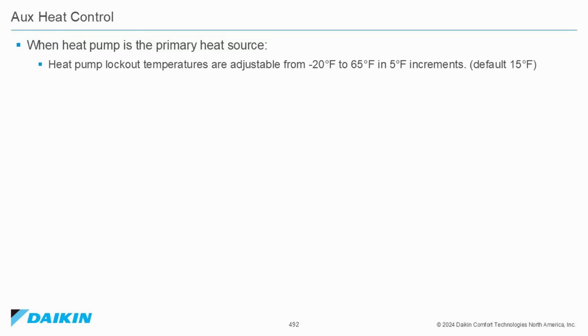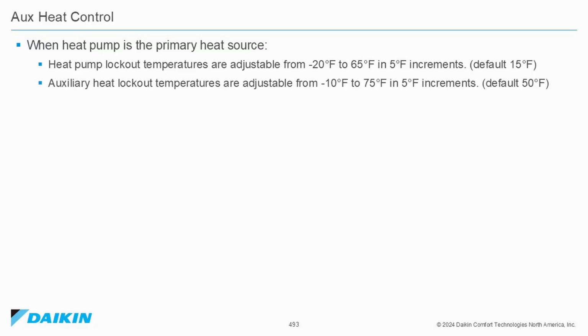Auxiliary heat control. When the heat pump is the primary heat source, the heat pump lockout temperatures are adjustable from -20 degrees Fahrenheit to 65 degrees Fahrenheit in 5-degree increments. The default setting is 15 degrees Fahrenheit. Auxiliary heat lockout temperatures are adjustable from -10 degrees Fahrenheit to 75 degrees Fahrenheit in 5-degree increments. Default setting, 50 degrees Fahrenheit.